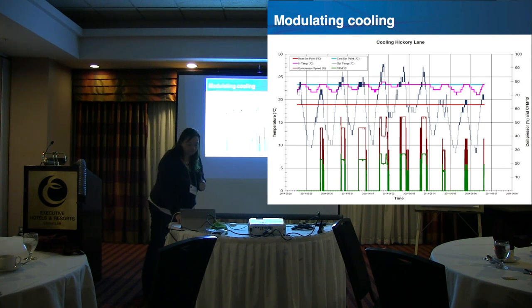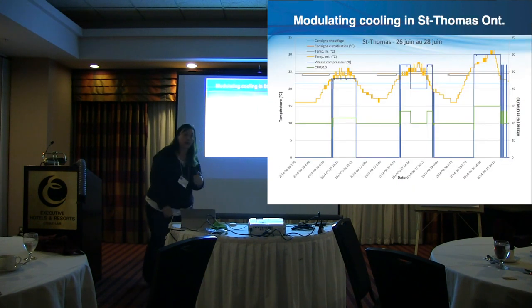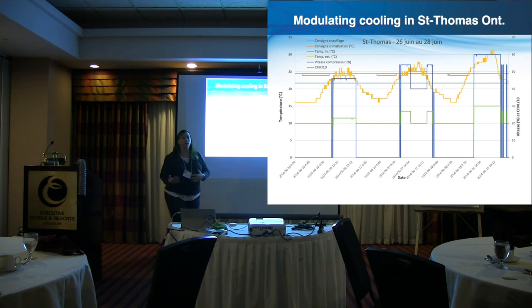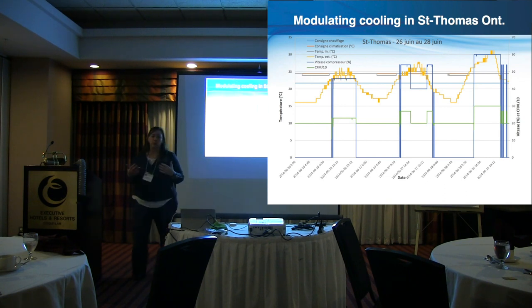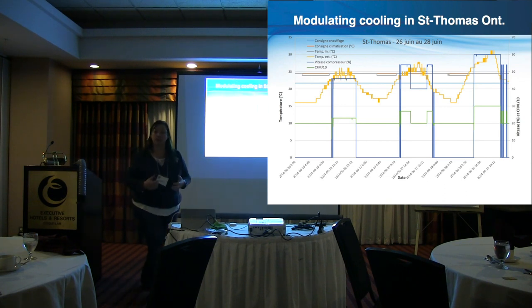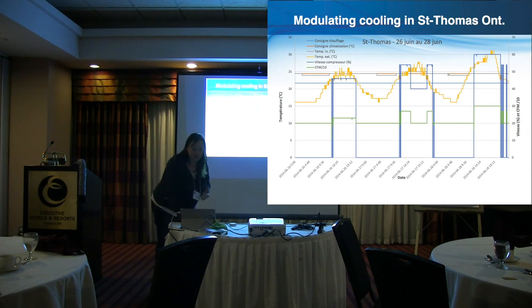no matter how long it's running for. So then Doug said, hey guys, I have an HRV, can we interlock it in? We said, okay. So now we interlock it in. So now instead of the system turning off when the house is at temperature, you'll see it doesn't matter what the system's calling for, heating or cooling, or just straight exchange, you've got continuous airflow there.